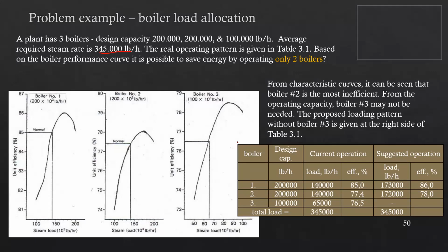So based on the boiler performance stated in these illustrations, in this graphic, the question is: is it possible to save energy by operating only 2 boilers? We need to compare using 3 and 2 boilers, based on the load and also on the boiler efficiency.